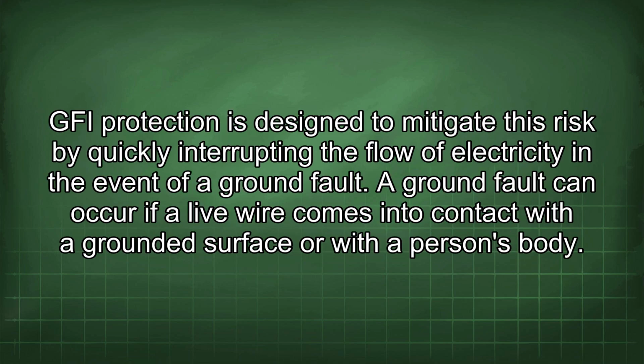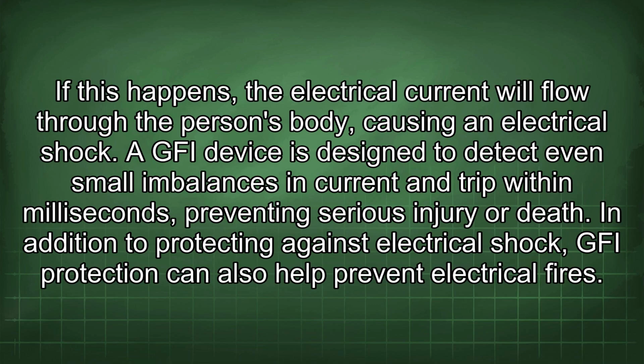GFI protection is designed to mitigate this risk by quickly interrupting the flow of electricity in the event of a ground fault. A ground fault can occur if a live wire comes into contact with a grounded surface or with a person's body. If this happens, the electrical current will flow through the person's body, causing an electrical shock. A GFI device is designed to detect even small imbalances in current and trip within milliseconds, preventing serious injury or death.